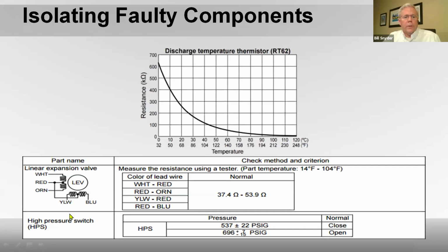Down here, this is a linear expansion valve, and it's telling you how to check it out. A linear expansion valve looks like a big coil on top. It's actually a series of 4 different coils in there, with red being your common. So you're going to take a resistance between white and red, red and orange, yellow and red, and blue. You should be getting a reading like this.